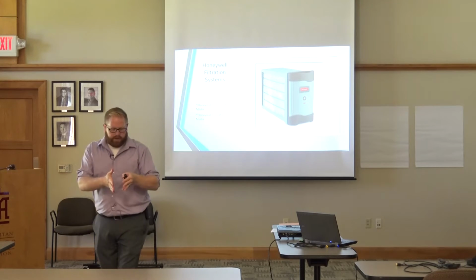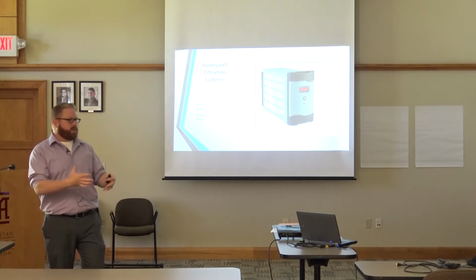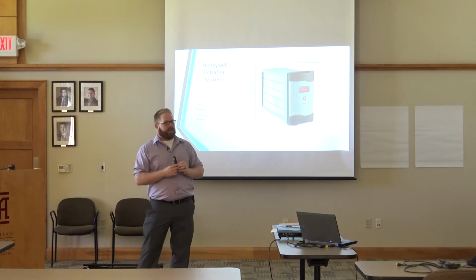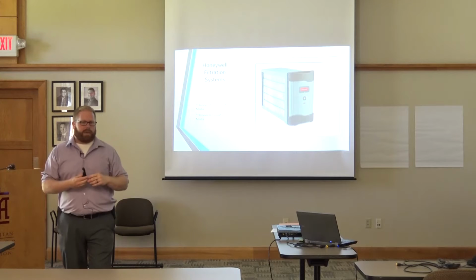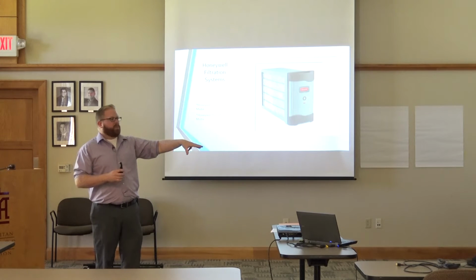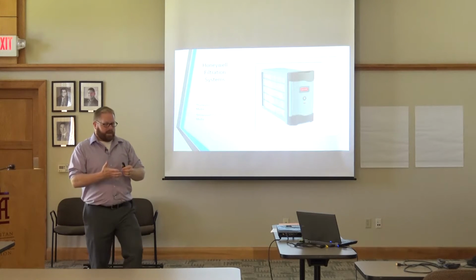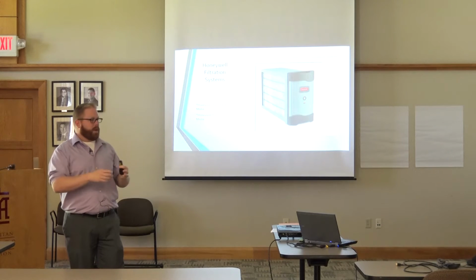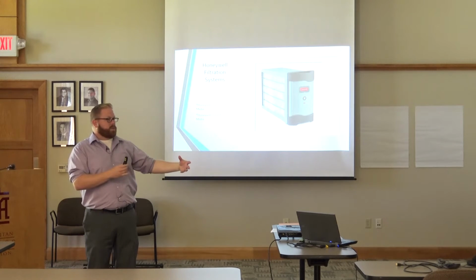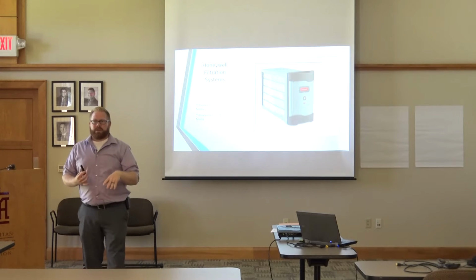One thing that will actually hurt zoning is what's called micro zones. I'll make the example. If you have a 2,500 square foot ranch, but you want to have your master bedroom on one thermostat. Well, between the bedroom, maybe the walk-in closet and the bathroom, you probably only have 4 heat runs as an average. So by zoning that master bedroom, depending on the piece of equipment that's chosen, sometimes you're overheating or overcooling those particular areas. If the furnace is just a single stage piece of equipment, it's coming on at full blast trying to maintain that master zone, which might only need, say, 10,000 BTUs, but the furnace is kicking on at 60,000 BTUs. So there are ways around it, like putting bypasses in, which is what we do as a standard.